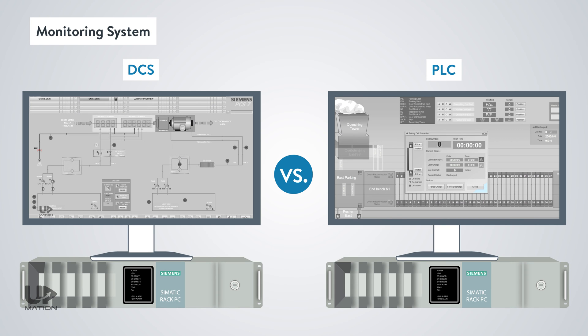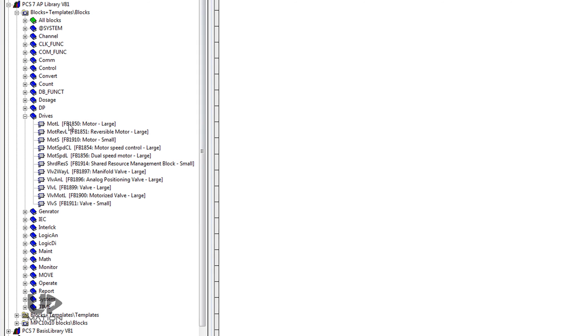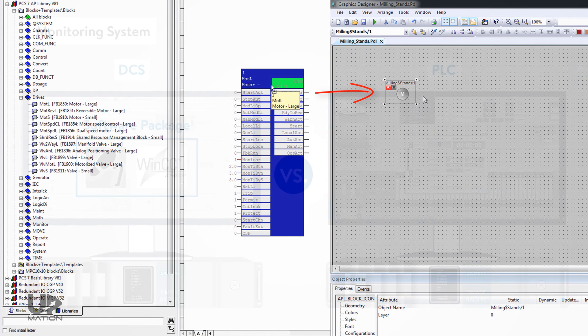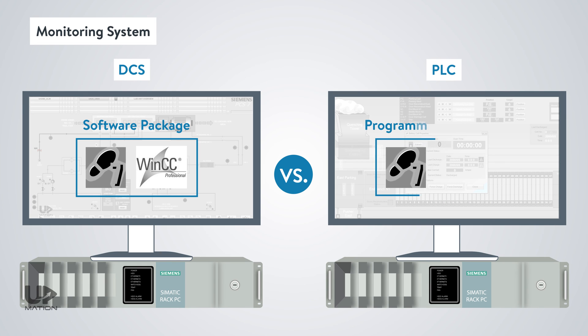Finally, there are differences in the DCS and PLC monitoring systems. In DCS, there is an integrated software package that includes a fairly complete set of monitoring facilities. By calling the control functions into the programming environment, the corresponding graphical objects are automatically added to the HMI pages with their addresses, saving precious engineering time. In PLC systems, however, there is usually no relationship between the programming and monitoring environments, and each needs its own time to be created and developed.